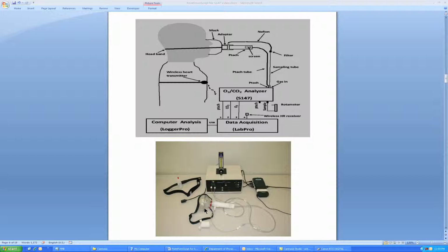The mask or mouthpiece is connected to the PTAC via a small adapter. The PTAC is the device used to measure the breath flow. It does this by measuring the small differential pressure created across the screen as the breath emerges to atmosphere.